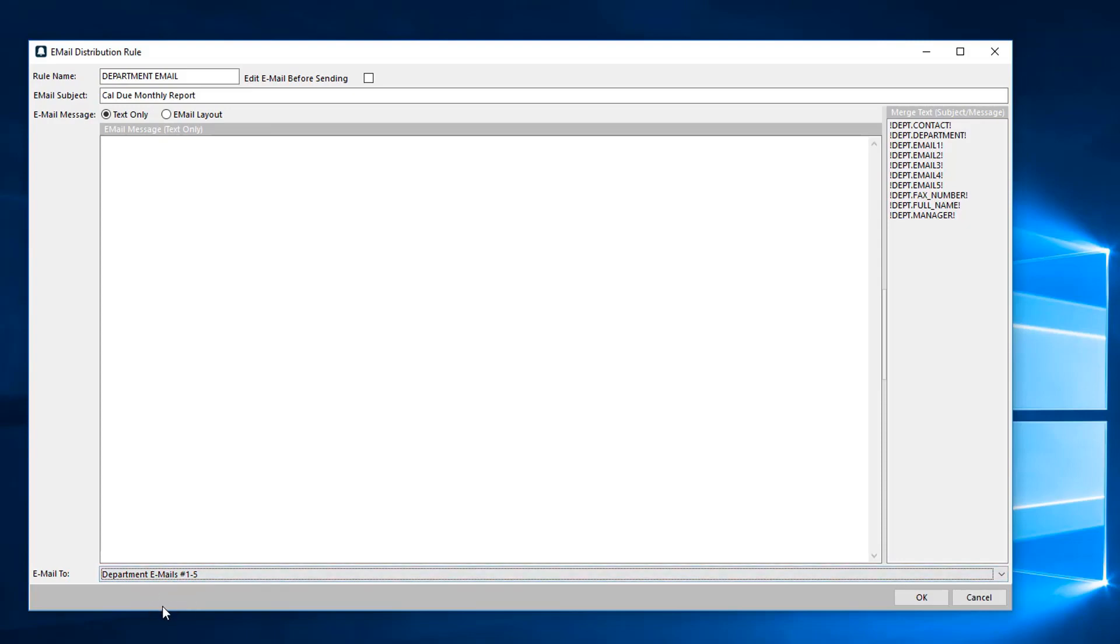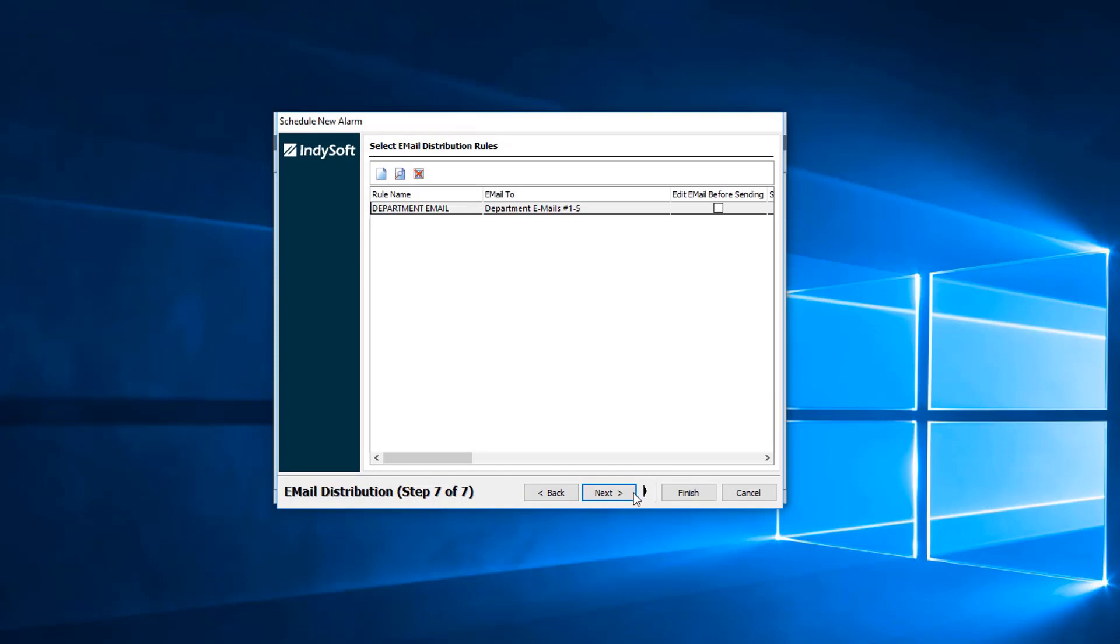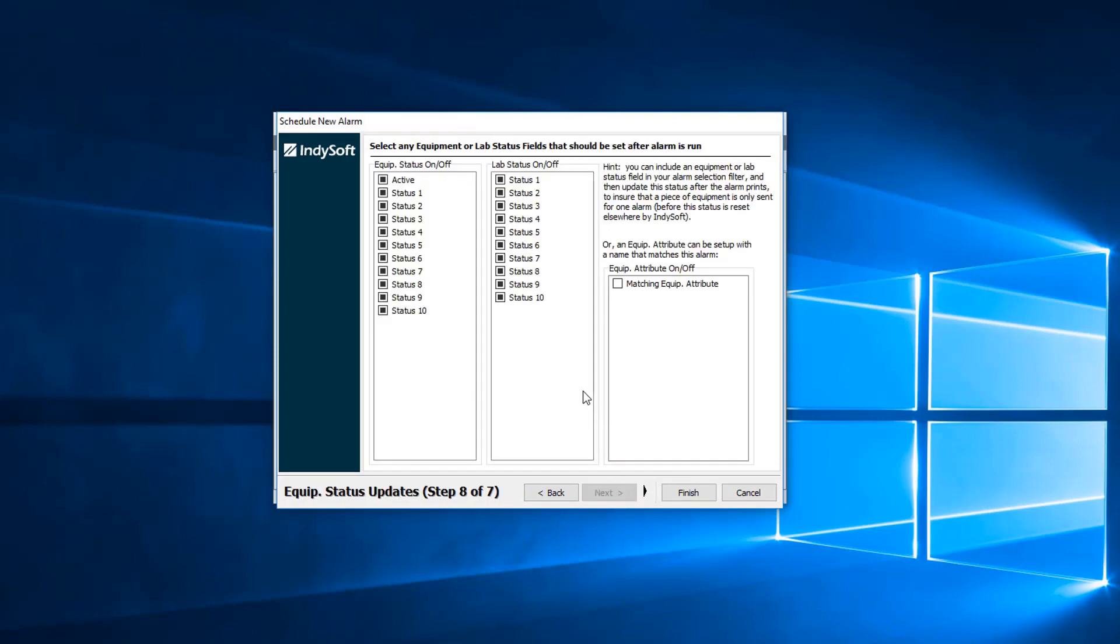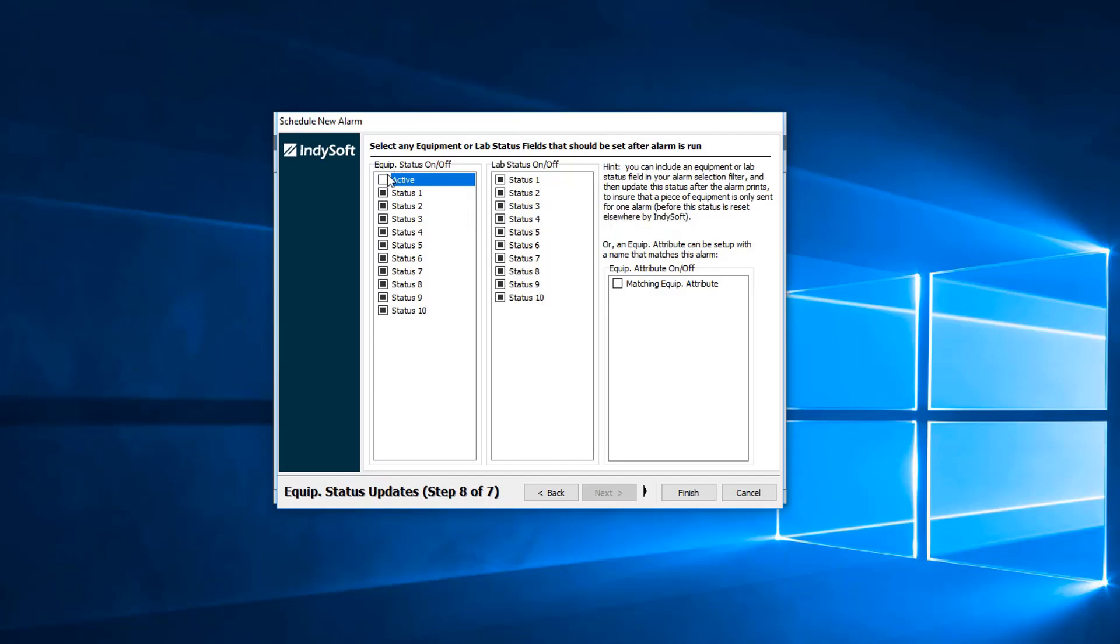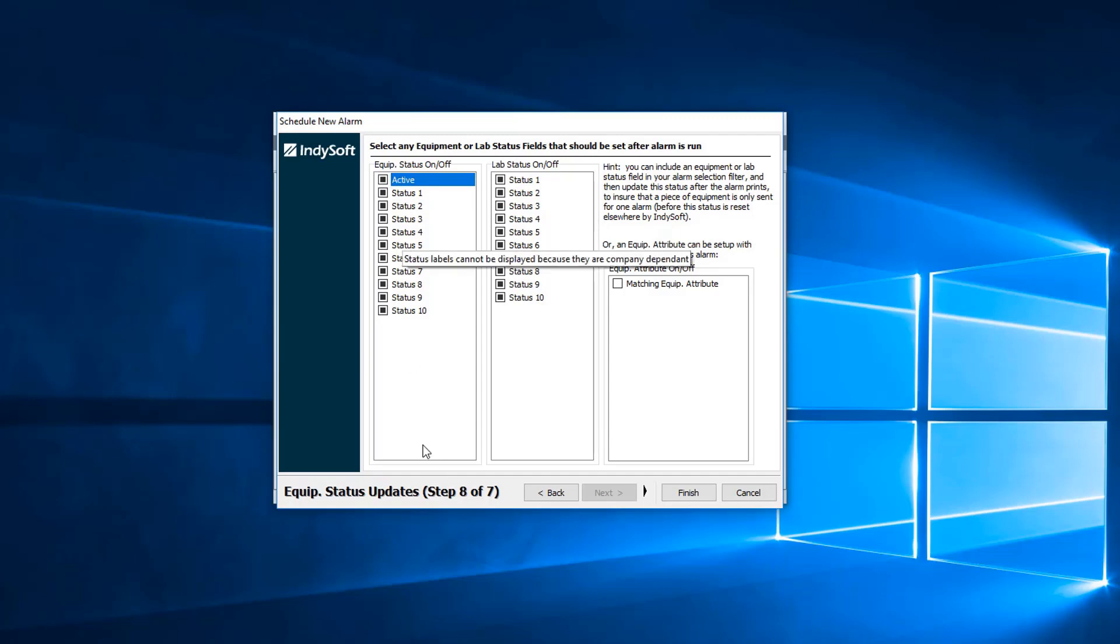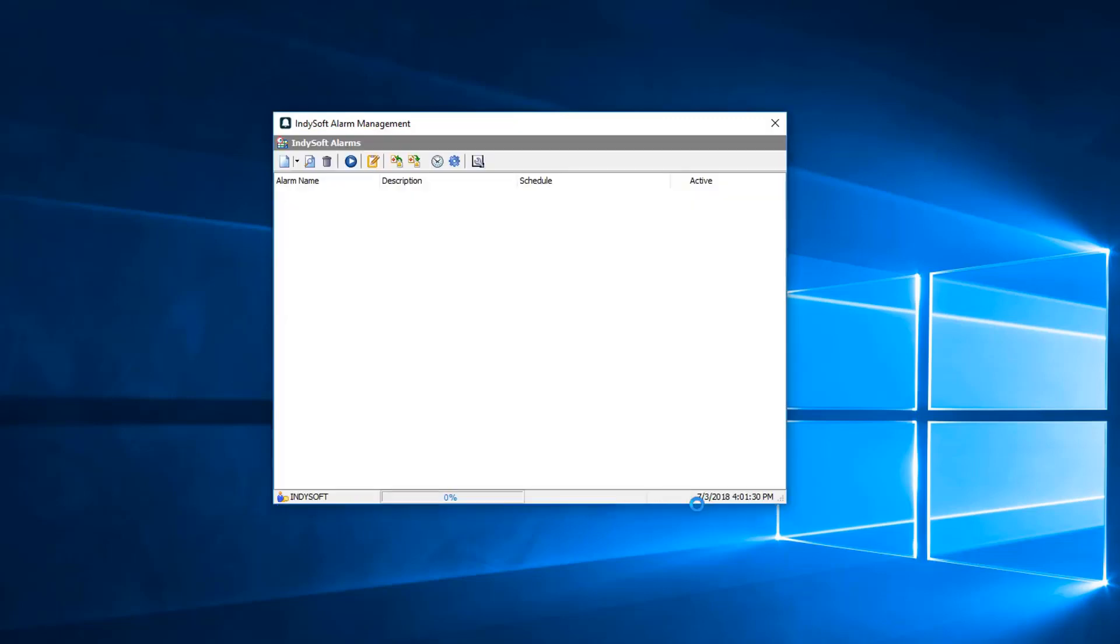We'll go ahead and leave department emails one through five and hit okay. Next, this is the option to select any equipment or lab status fields that should be set after alarm is run. After this alarm is run, if you wanted it to activate all the equipment that it grabbed or deactivate all the equipment that it grabbed, that's up to you. After we're done with that, we go ahead and hit finish, and then it added the alarm to this section.